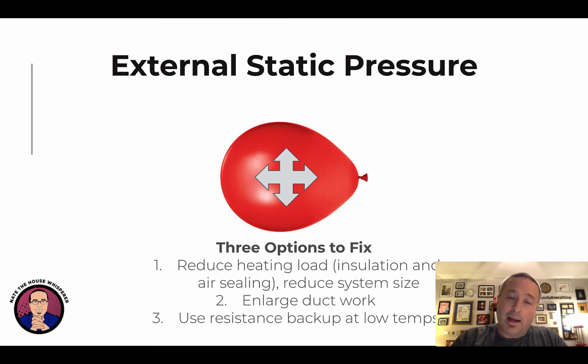So there are 3 options to fix static pressure. The first one is we reduce the heating load so that we can downsize the system. And I'm going to show you that more or less happening in a minute. But that is done with insulation and air sealing. That is building shell work, which we're going to be talking about after the HVAC section here. So that's the first option. You reduce how much it takes to heat the house. Second option is you make the ductwork bigger. That can be possible, and a lot of improvements can be made at the equipment, or near equipment changes, as they're known as.